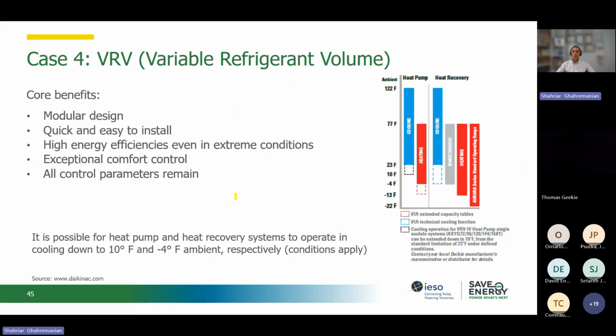So if we have a VRF system, the core benefit is that it's a modular design. That's one benefit. It's quick and easy to install because it's a brand new building design. It's really good to consider this one. It's very energy efficient, even in extreme conditions that we might have. And it provides exceptional comfort control because the temperature fluctuation is much less than the conventional system, and all control parameters remain the same. So if it's possible, it's better that we consider heat recovery, because it provides more efficiency to the system.